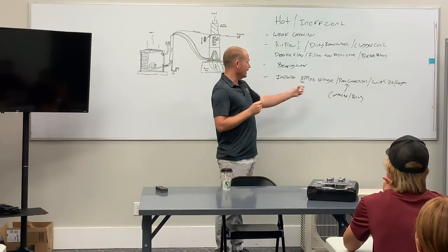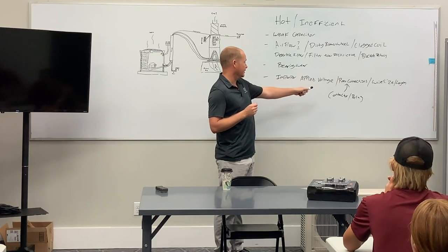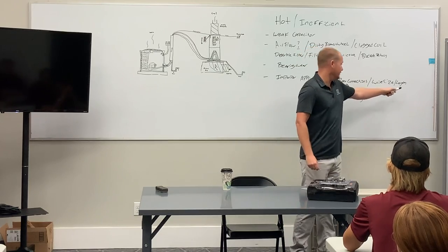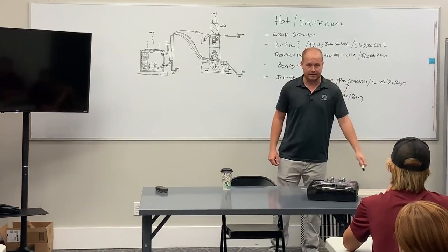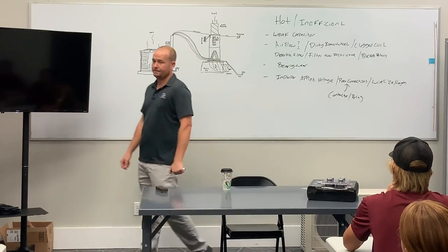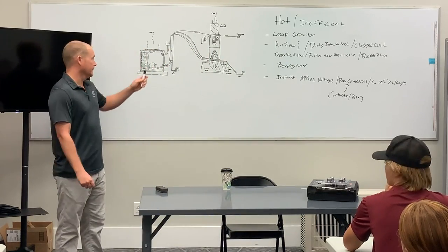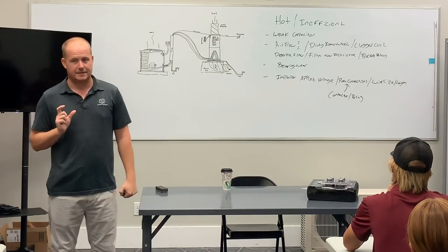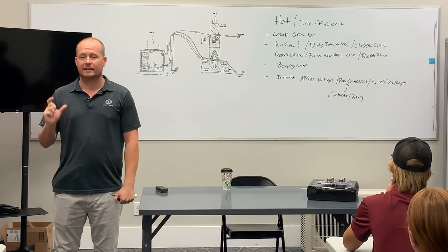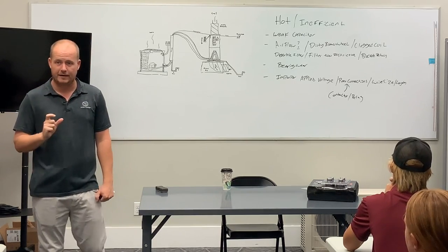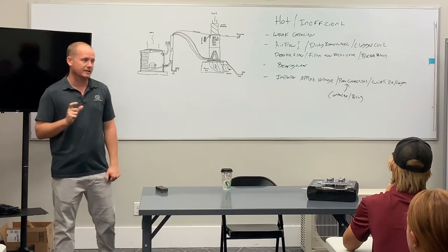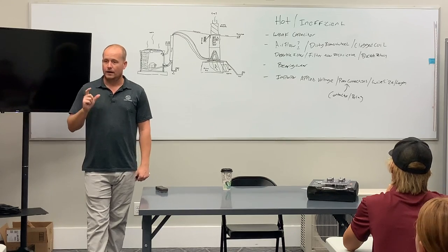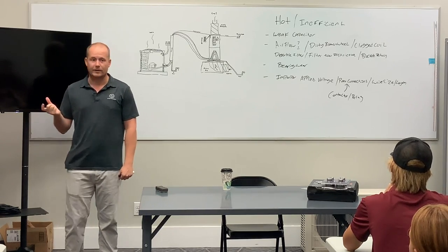A lot of these things here are adding resistance. In fact, all of them. Poor connections, wire size being too small, length being too long, contactor or relay contacts not making good connection. Those are all things that can lead to hot and inefficient motors. I want you to get your head really clear when you're communicating to a customer about these problems, because a customer doesn't really care so much about the technical name for the parts that you're replacing. Of course, they want to know you're not scamming them, so that's why we don't make up names for things.